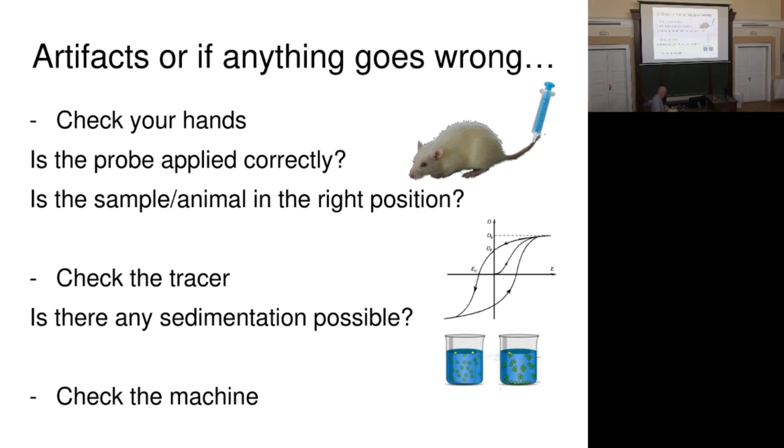I remember a quite funny experience. It was with MRI when I first saw high field MRI for animals. We tried this on an orange, which we put inside, and made some localizer, it was nice, and then we made some further sequences and there was no signal. It was very simple because of the vibrations of the gradient system. The orange rolled out, so check the position. Usually it's one very easy mistake and easy to correct.